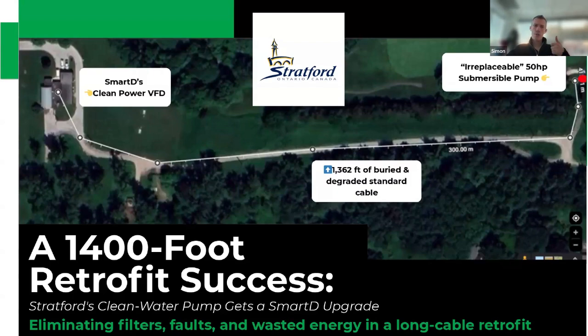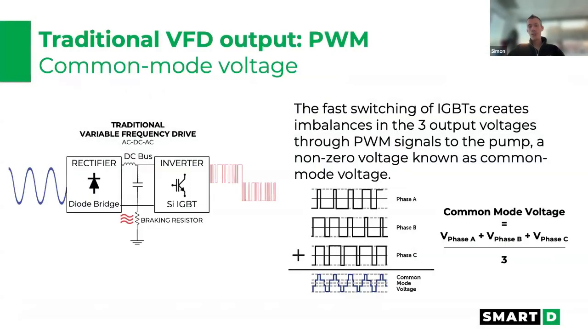Now, we've talked about harmonics, we've talked about voltage spikes. There is a third killer here, which is common mode voltage. And you've seen it quickly in Roger's video. Common mode voltage is caused when your three phases are not perfectly balanced. If you have three sine waves, the sum of these three sine waves is 0, and so you don't have that common mode voltage. In the case of a PWM, those are square signals. They don't add up properly, and you have a non-zero common mode voltage.